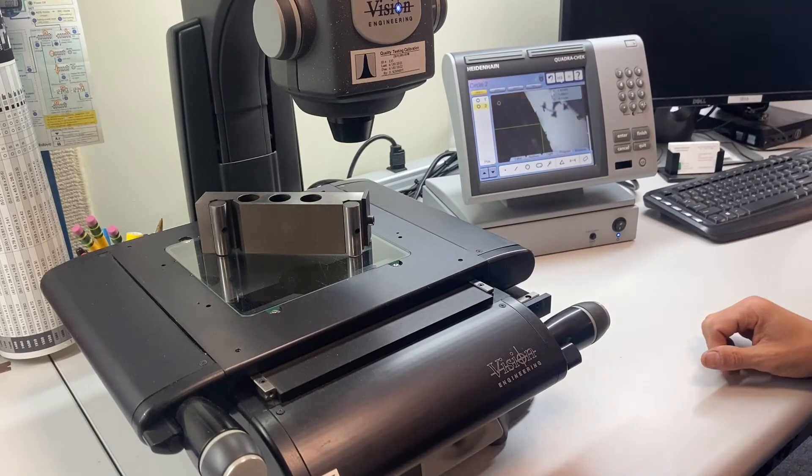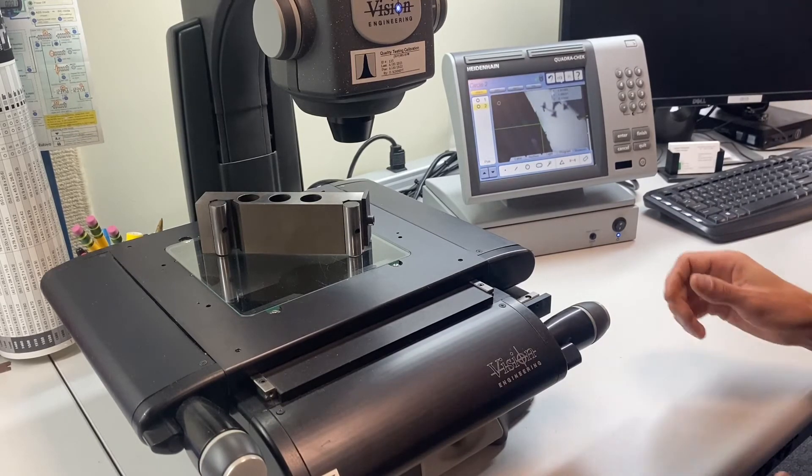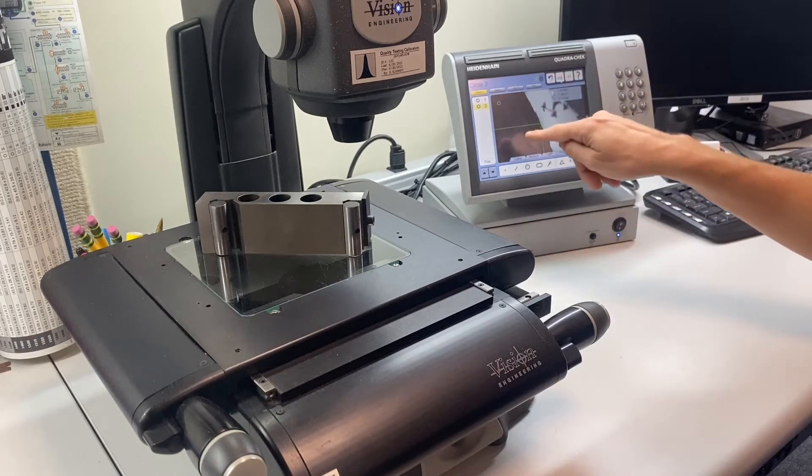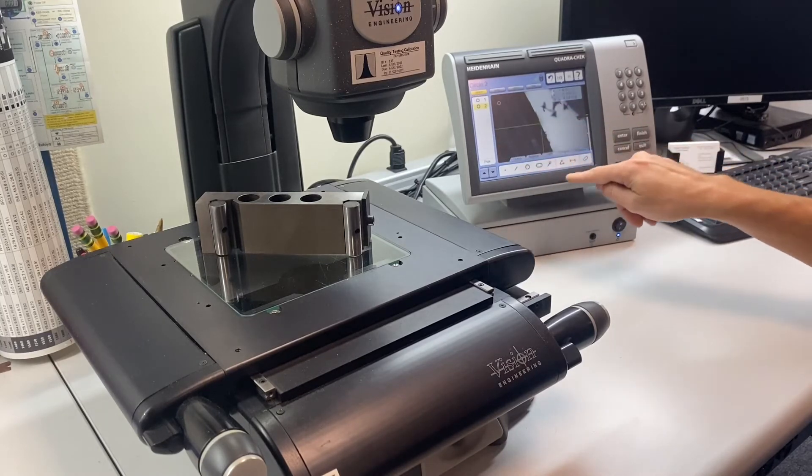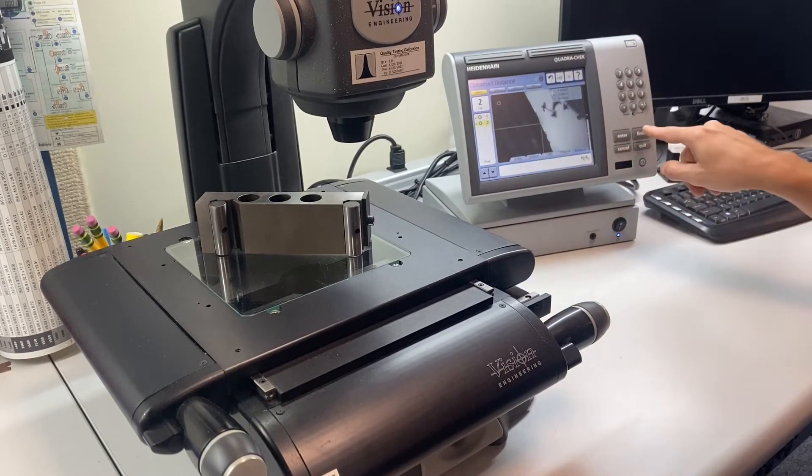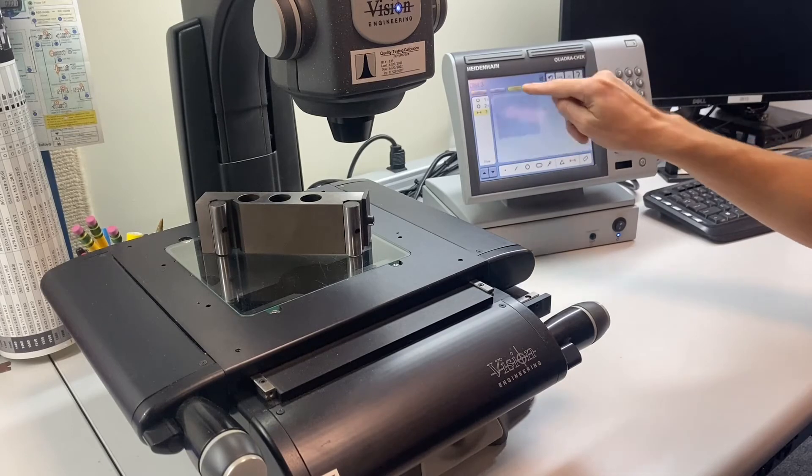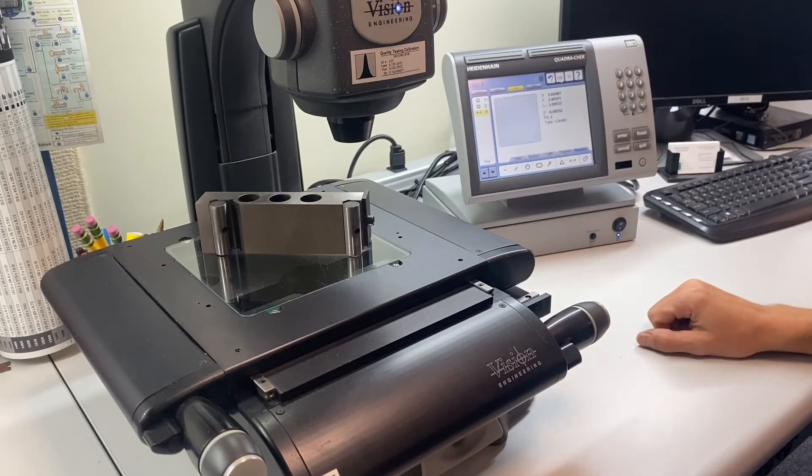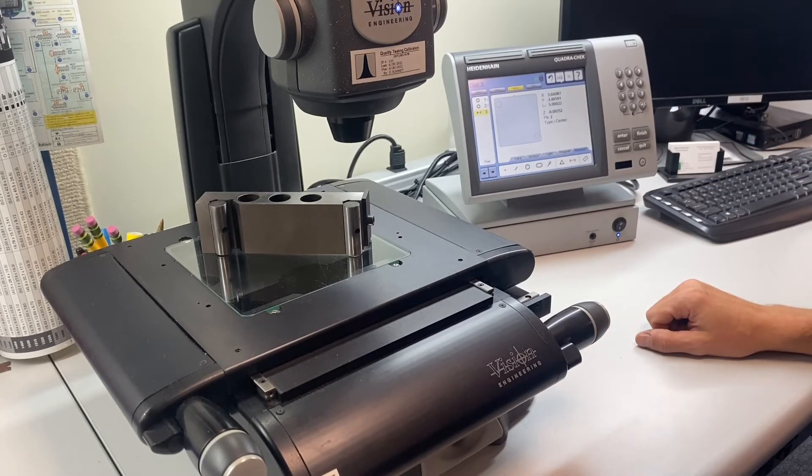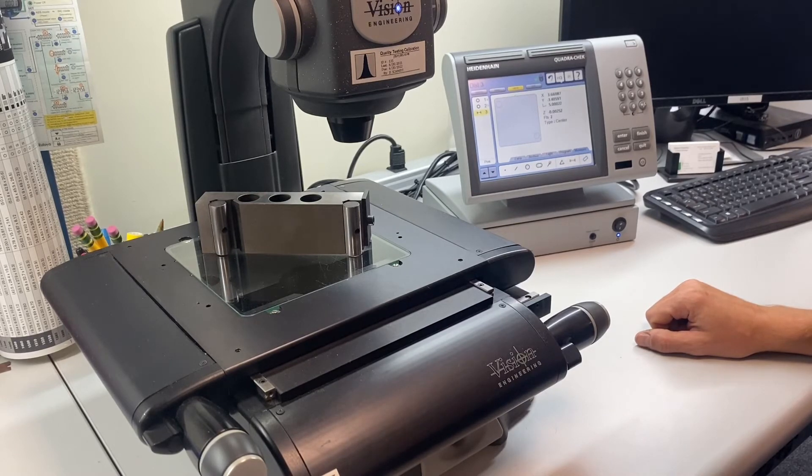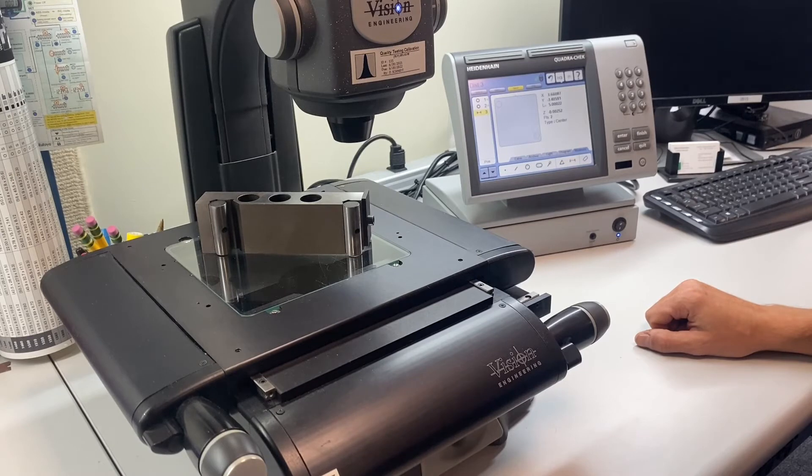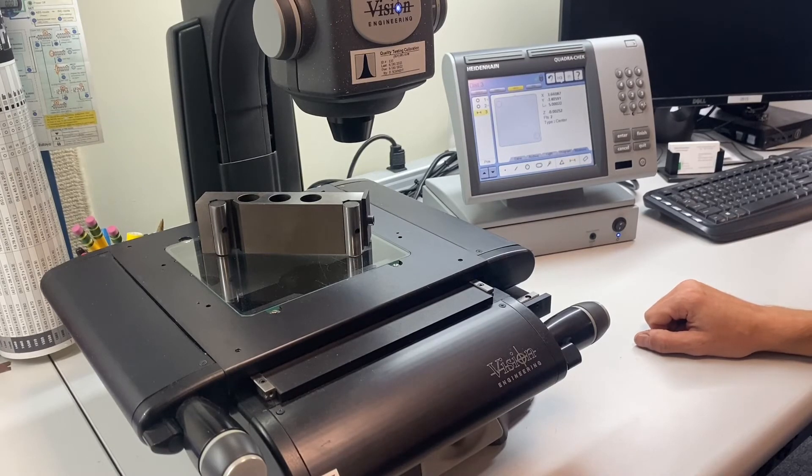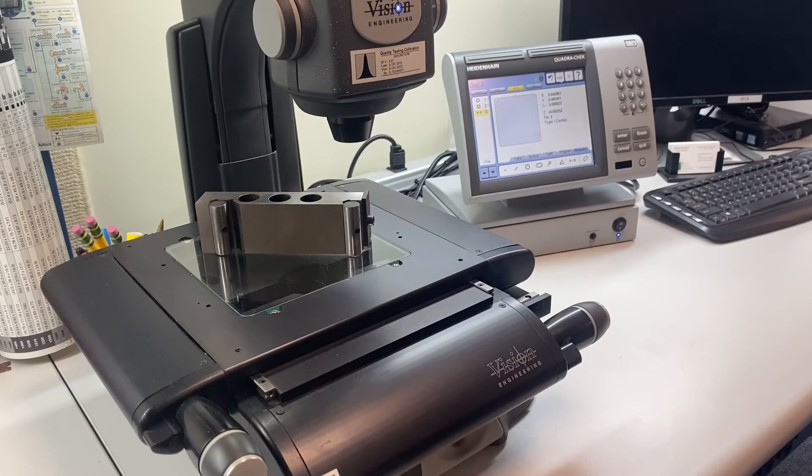We get 0.62454. Lastly, we will measure the distance between these two pins and we get 5.0022. This should be a five inch distance and we measure it to be within two tenths. That concludes the first step of calibrating a sine bar.